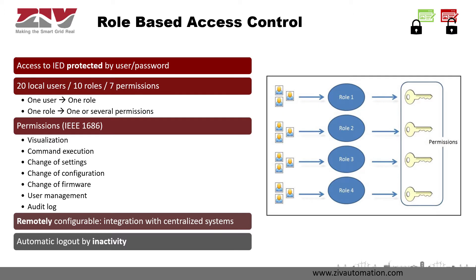The IED has also the possibility of defining roles, up to 10, and each role can have up to 7 permissions assigned. One local user will have one role assigned, and one role will have one or several permissions. The available permissions are strongly based on IEEE 1686 and allow limiting the information and operations a user can access and perform.